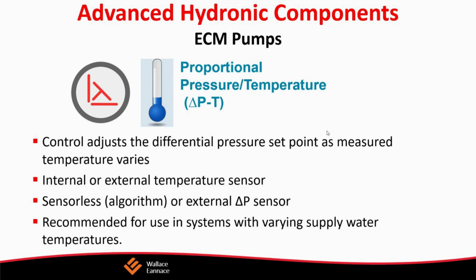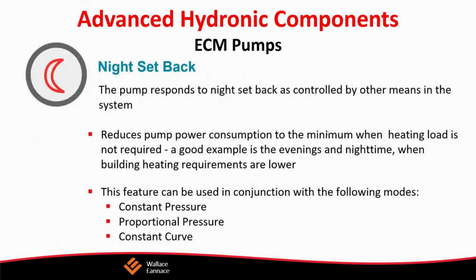Proportional pressure. Pump pressure continuously adjusts based on flow rate. The pump head decreases as flow rate decreases. Maximum pressure is easily set from the pump interface. It has, again, a sensorless algorithm, or it can be used with an external sensor to create a delta P, a change in pressure sensor. It's recommended for use in systems where pressure varies with flow rates, as in hydronic systems using zone valves.